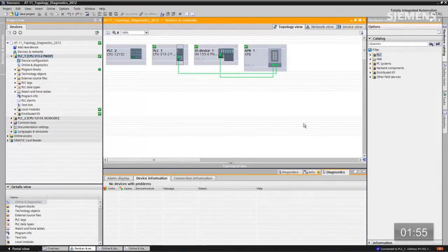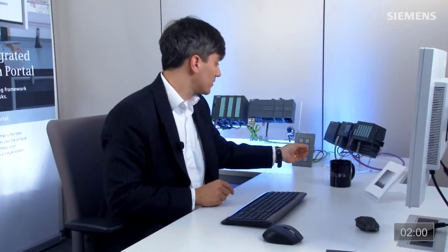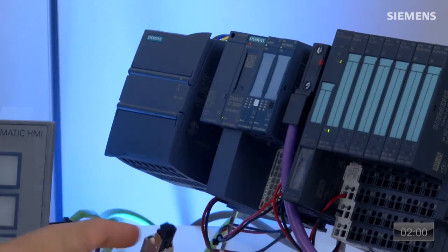Here I can see all the physical connections between all the field devices, and everything's green, and I got a check mark, everything's fine. All I have to do now is create a physical layer fault. I'm going to pull Profinet at ET 200SP. I'll physically see a red connection between the two, and there's all kinds of error handling going on in the background.